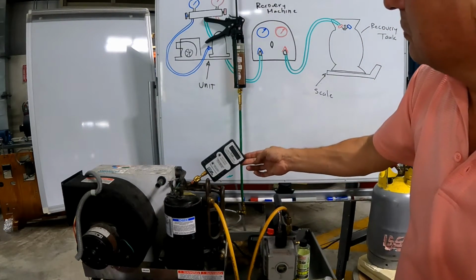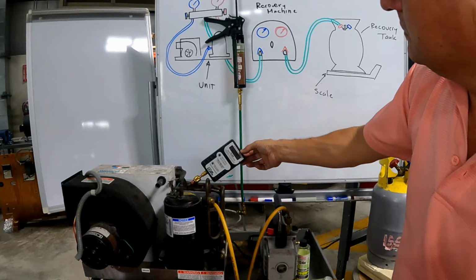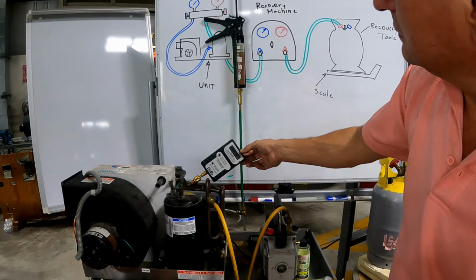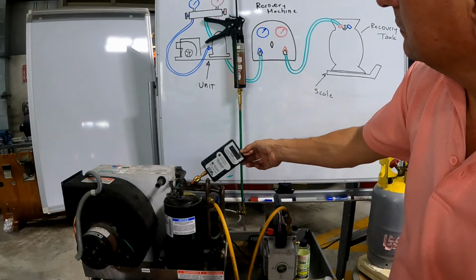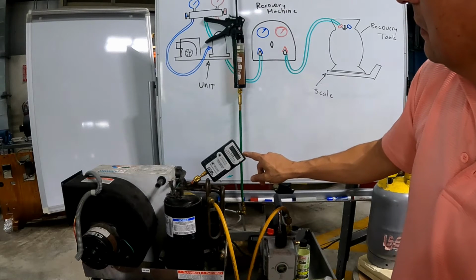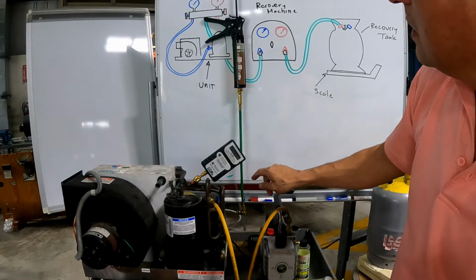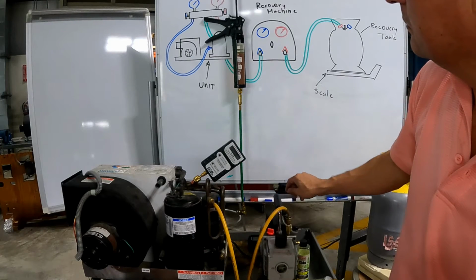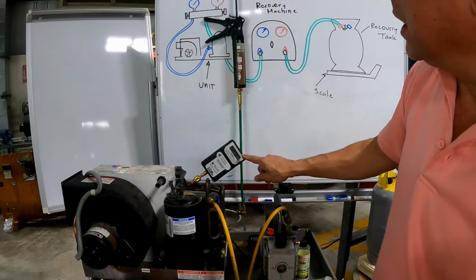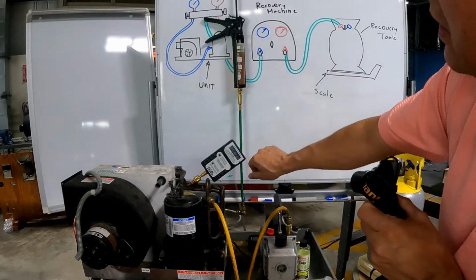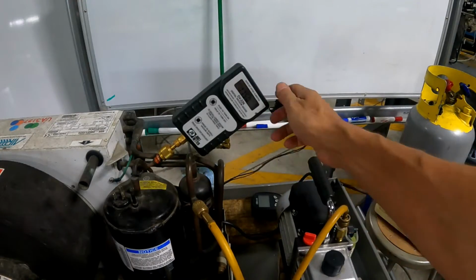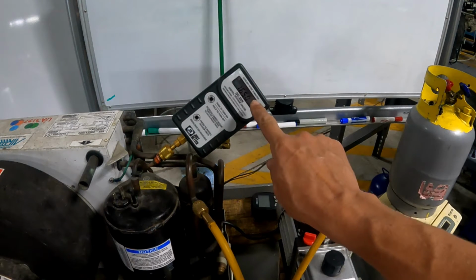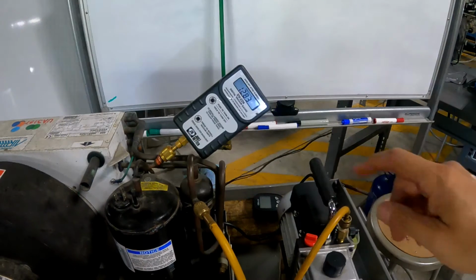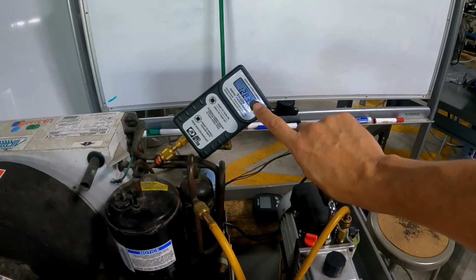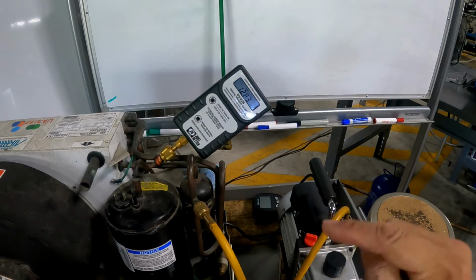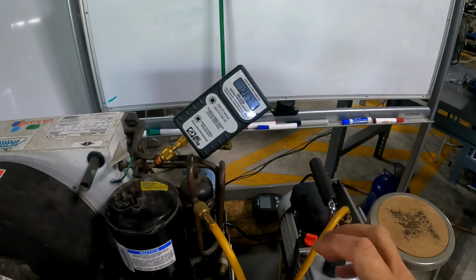At this moment it is 3000. 2,900, 2,800, 2,600, 1,700 microns, 1,600 microns. Now 1,200 microns. And the process continues going down, down, down until 500 microns.